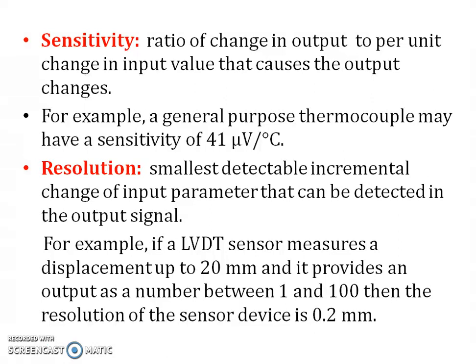Resolution is the smallest detectable incremental change of input parameter that can be detected in the output signal. For example, if a LVDT sensor measures a displacement up to 20 mm and it provides an output as a number between 1 and 100, then the resolution of the sensor device is 0.2 mm.